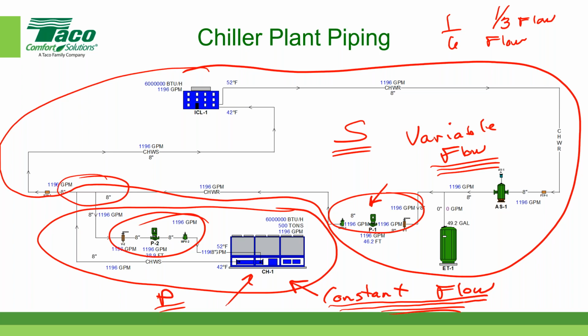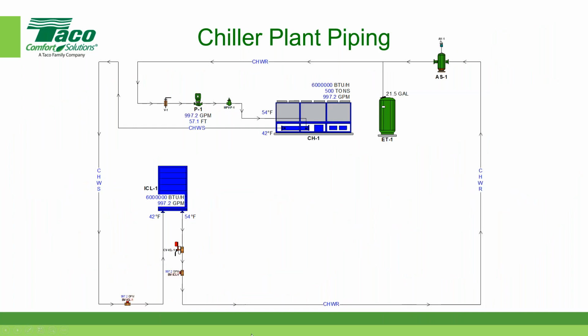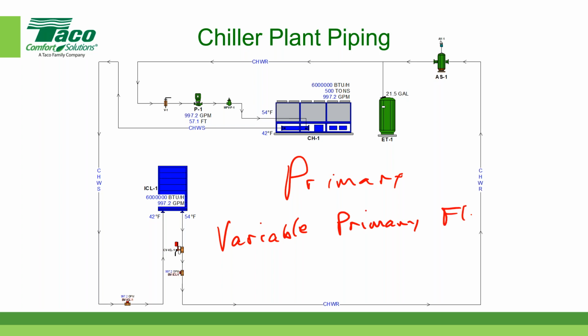What does just a primary pumping system look like? Let's go to the next one here. So this is a primary pumping system, and sometimes referred to as a variable primary flow. Now here the restriction is in terms of the minimum flow allowed by the chiller, which would typically be whatever the chiller manufacturer is telling us. Now, chiller manufacturers have a variety of ranges for chillers today, but let's assume for a moment, we're just picking a number, we know it could be less, but let's assume that the chiller could go down to 50% flow, all right?